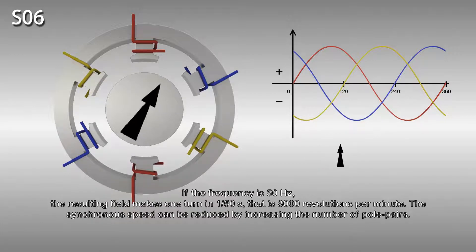If the frequency is 50 hertz, the resulting field makes one turn in one 50th of a second, that is 3000 revolutions per minute. The synchronous speed can be reduced by increasing the number of pole pairs.